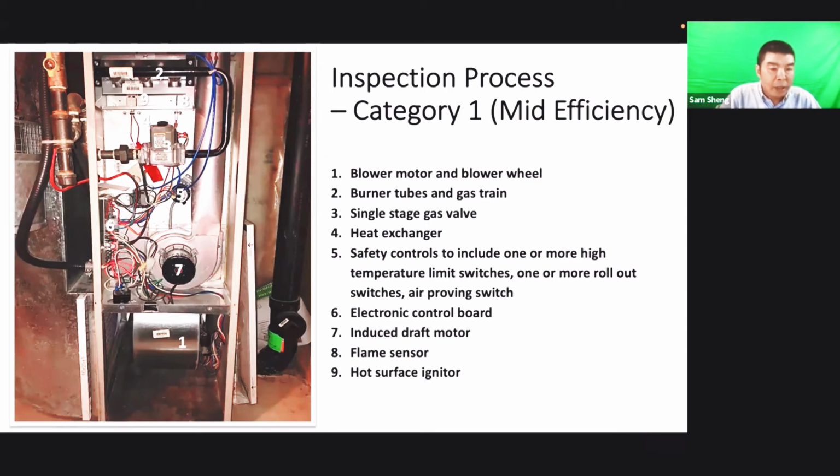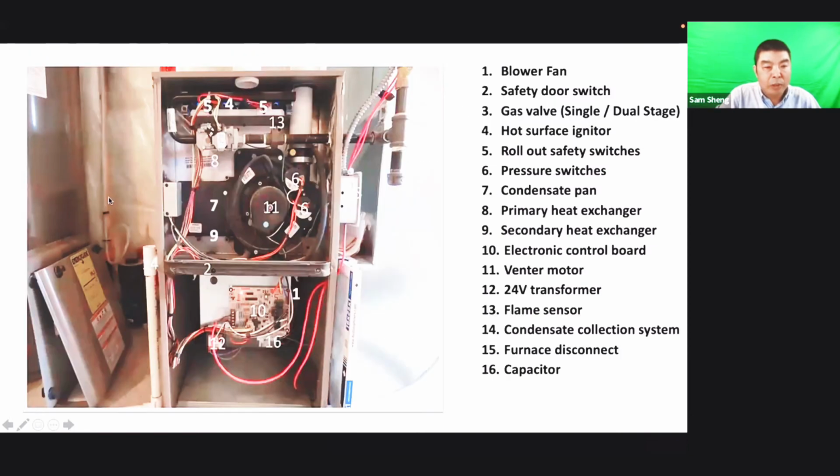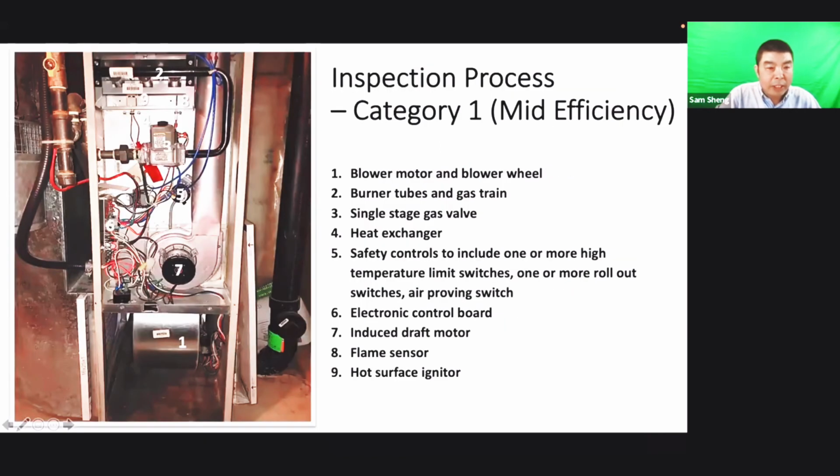Sometimes we can see dust or debris around the control board, especially if the control board is installed horizontally, on the top, and not vertically. It's easy to accumulate the dust. If there's dust there, it should be cleaned, otherwise some parts will overheat and then burn.